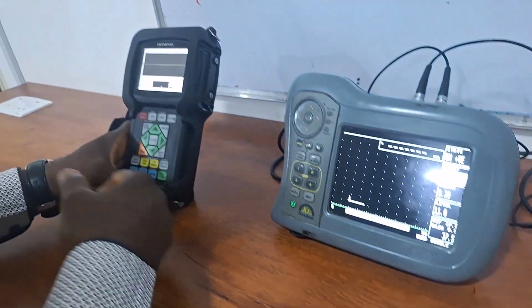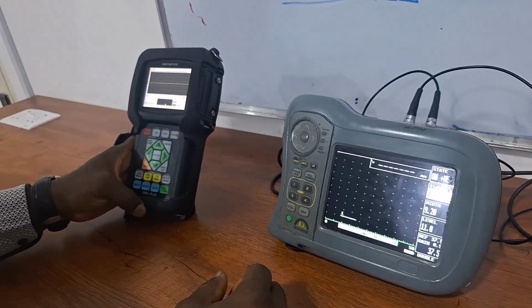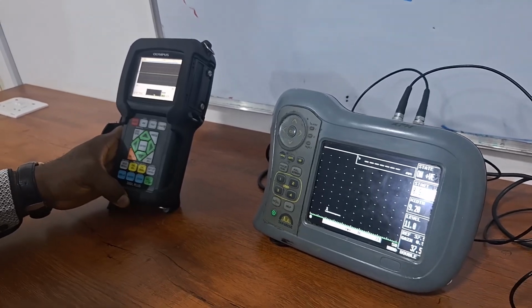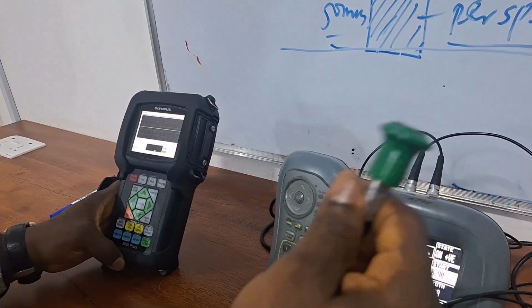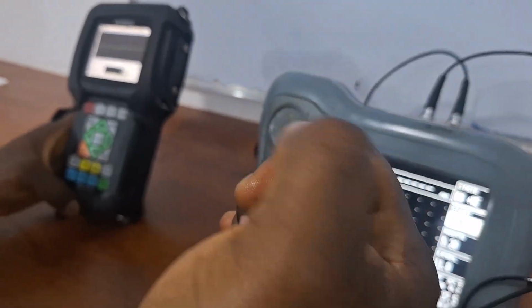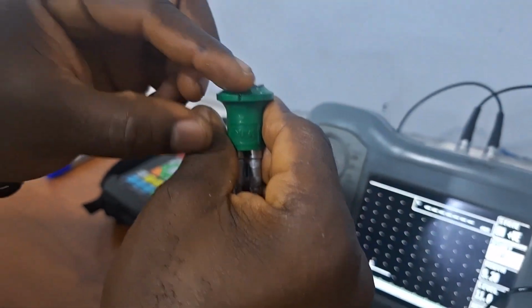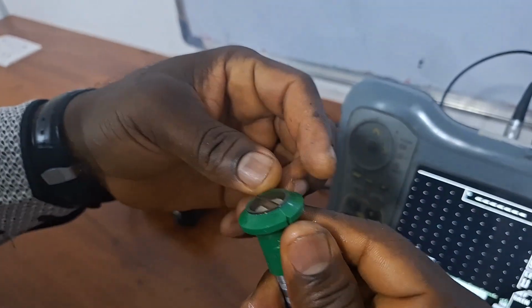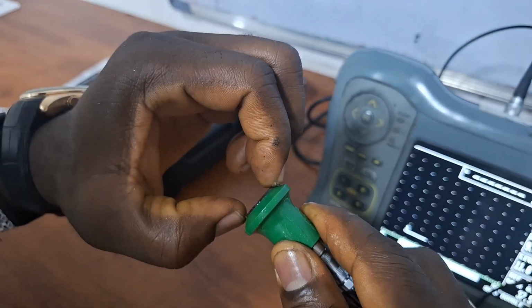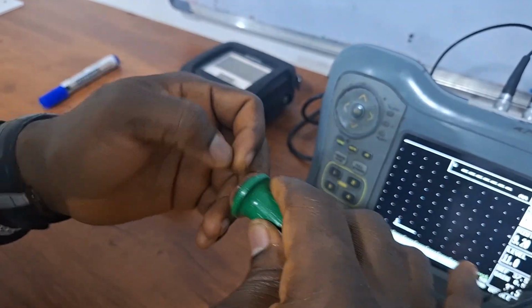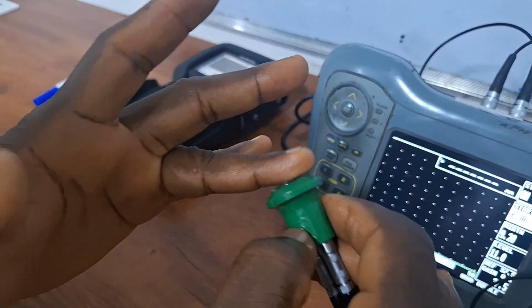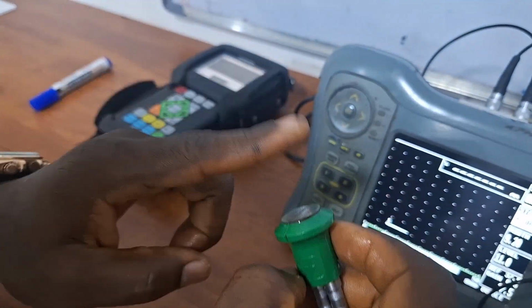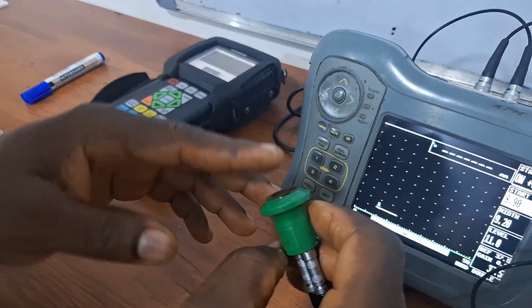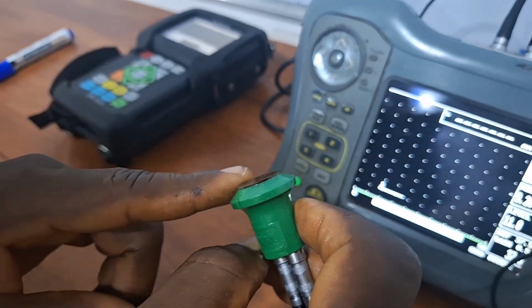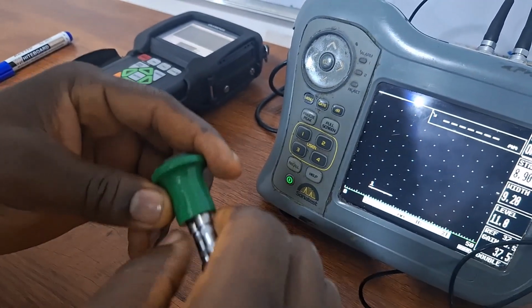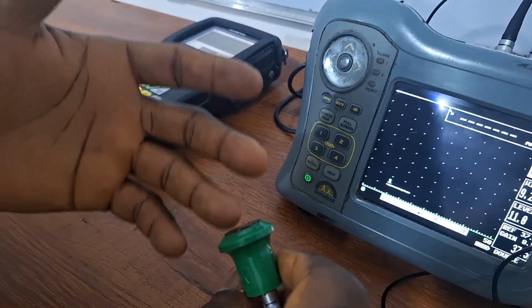I'm going to use two units, 39DL and Sonatest D-10. If you look at this, your probe, this is the shoe that we're talking about. If the temperature becomes very high, this is a perspex glass, not designed for very high temperature, it can melt. And then the material you are taking, the thickness also, it has the ability to burn off this probe shoe. So for very high temperature, for say 500, 200 degrees Celsius, this probe will not be used. You need to use a high temperature probe. And of course, you are going to add your high temperature couplant.